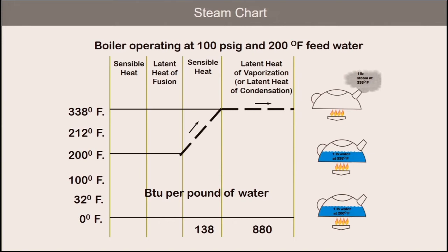Let me show you with this steam chart what I mean. Note we have a boiler operating at 100 PSIG, and the temperature of the feed water is 200 degrees, and the saturation or boiling point at 100 PSIG is 338 degrees Fahrenheit. This means I have to add 138 BTUs to each pound of water to raise the temperature to 338 degrees — one pound of water, one BTU, one degree, because the specific heat of water is 1. Now, once at 338 degrees the water is saturated, and if we want steam at 338 degrees, we need to add 880 BTUs to each pound of water in the boiler. Once we've done that, we now have steam at 338 degrees because we added the 880 BTUs of latent energy.